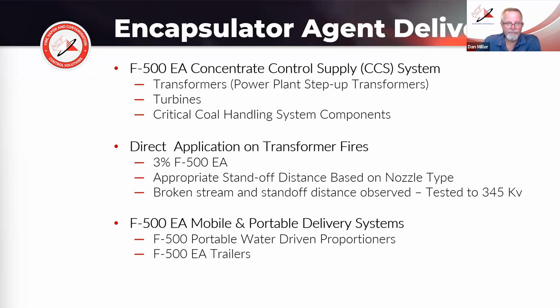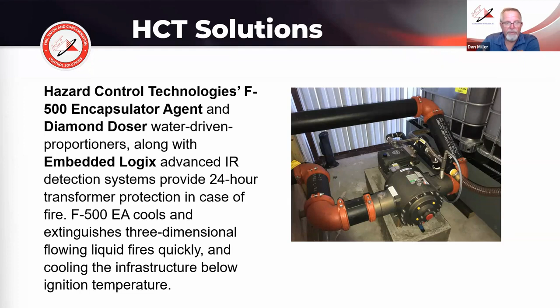This is a diamond doser, water-driven proportioner, typical installation. As you can see, the concentrate tanks over on the right, they're just totes on a leak catchment basin. It's just fed into the water-driven proportioner. As water travels through the riser, it proportions agent into the riser at the appropriate percentage as it's set. And then when you use advanced detection systems like those by Embedded Logix that we partner with, it helps cool any kind of fire really, but three-dimensional fires, liquid ignitable fires, fires discovered in conveyor belts and so forth very, very quickly, and transformer fires.